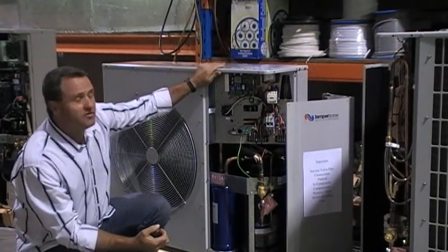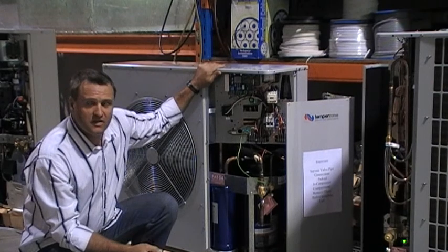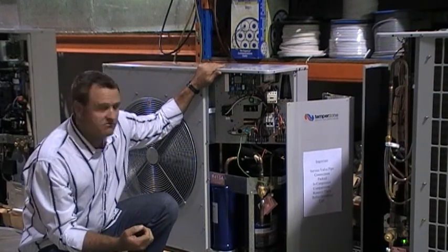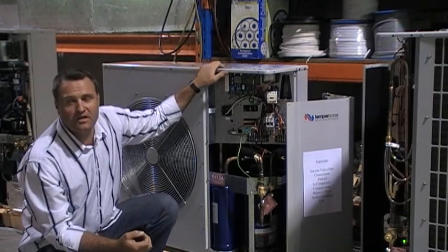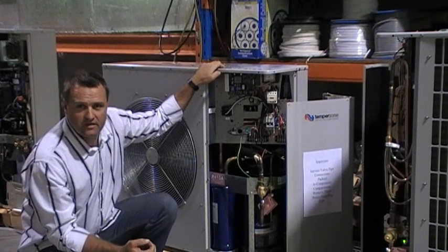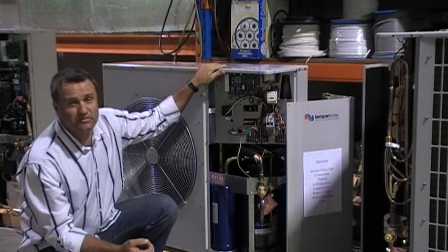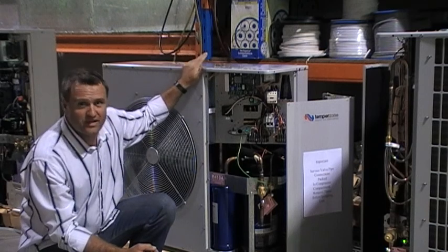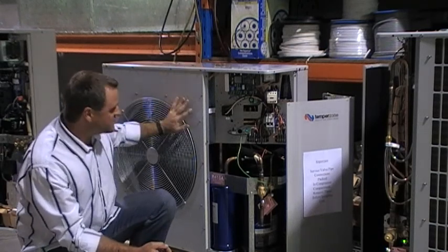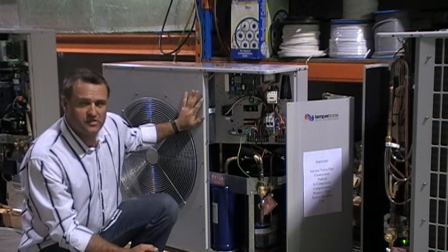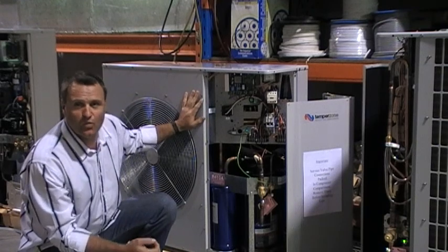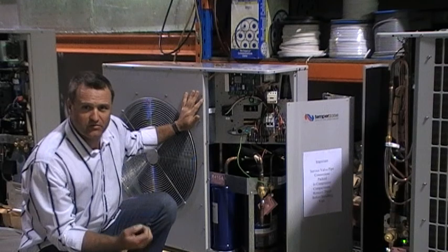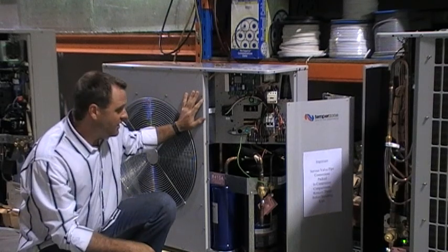The shell itself is galvanised and powder coated, so that even if corrosion did make its way through the powder coating, it hits a zinc protective layer over the steel. So what you're getting is a unit that isn't going to rust away. And the fins on the Temperzone unit are also epoxy coated, so the aluminium won't powderise in a corrosive environment as well.